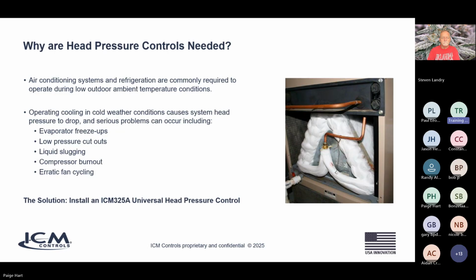So operating cooling in cold weather conditions causes the system head pressure to drop. Pressure and temperature are directly proportional, so as the temperature outside decreases, the pressure in your system also decreases. It can get low enough that it's damaging to your equipment. You can have low pressure cutouts, evaporator freeze-ups, liquid slugging of the refrigerant, compressor burnout, and erratic fan cycling if you don't have head pressure controls like the ICM325A. So the solution is to install an ICM325A head pressure control to control that fan speed.